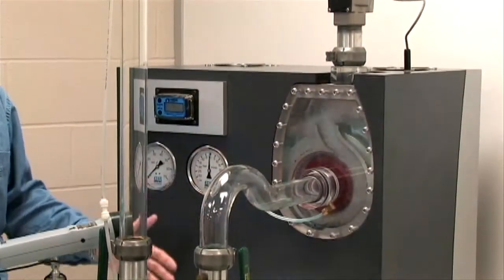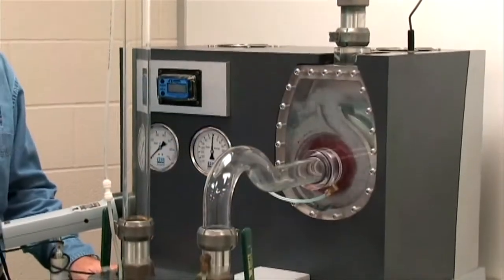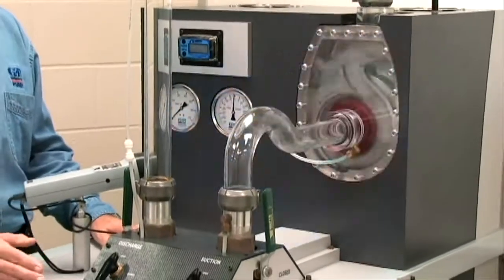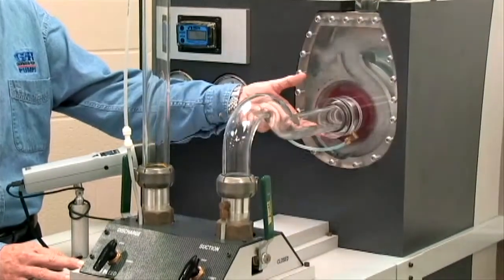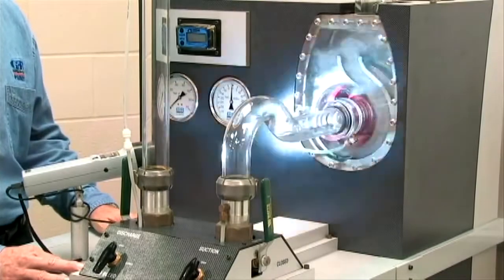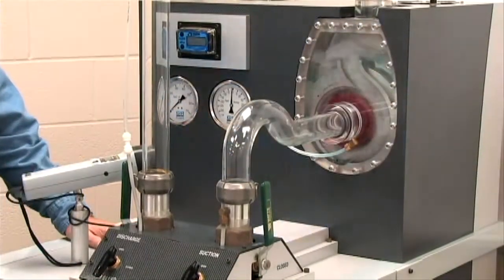Due to differential in pressure, atmospheric pressure that we live around every day is higher than the lower pressure created at the eye of this impeller. Due to that differential in pressure, atmospheric pressure outside begins to force liquid up the suction pipe.